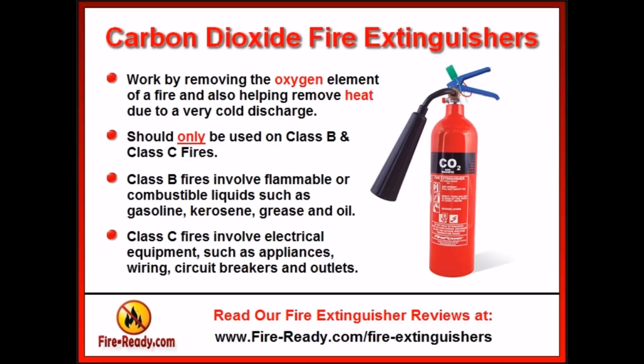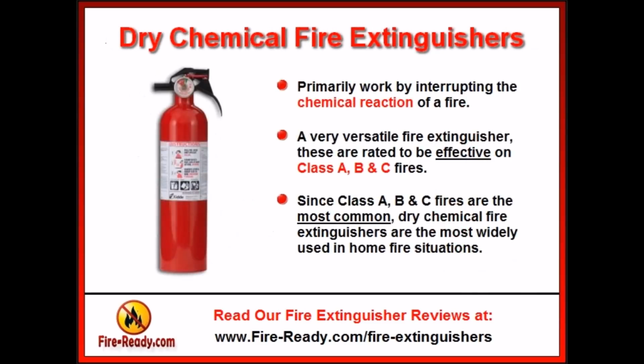Carbon dioxide fire extinguishers work by removing the oxygen element of a fire and also helping remove heat due to a very cold discharge. Carbon dioxide fire extinguishers should only be used on Class B combustible liquid fires and Class C electrical fires. Dry chemical fire extinguishers primarily work by interrupting the chemical reaction of a fire.